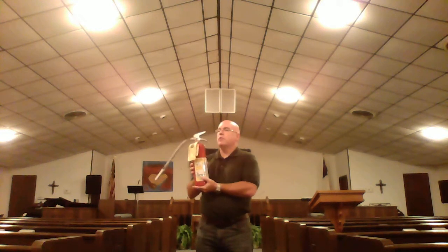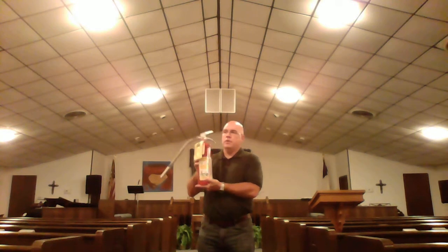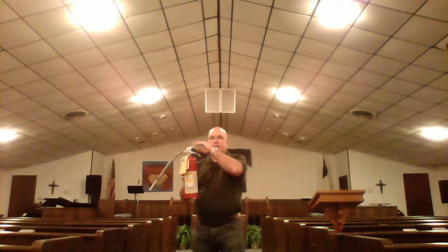Can I refill these? is a common question that we get. Yes, if you have one with a metal head like this, they can be refilled, although it may be just as cheap to replace them. That'll be something you'll have to check. Also, these have to be hydrostatic tested about every 10 years. If you've got one at home that's 10 years of age, get rid of it, replace it. Just get you a brand new one. If it's got a plastic head on it like this, it can't be refilled. You're going to have to go ahead and throw that away and buy a new one.